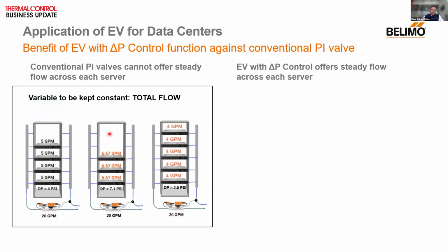But in the second case, when racks are reduced, delta P is also increased and flow is also increased because your inflow is the same. This is when racks are decreased, and this is when racks are increased. Again, 20 GPM is the same flow, where you can see the different values of flow and pressure.